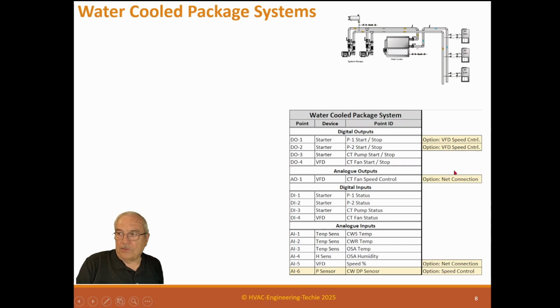Now you can also do a net connection here, so you can run a network to a VFD, and you can suck up all its points. I mean, they may have 20, 30 points that you can suck up. However, you should always have at least one hardwired start-stop to a device, in case you have a burp on the network. Maybe the IT guy takes the network down to work on it, and all of a sudden you can't turn it on and off. That's a bad deal.